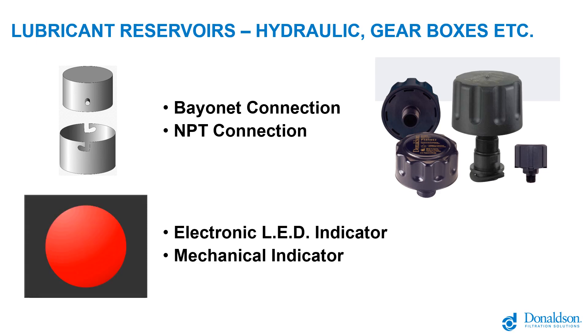There are also two indicator types: an electronic LED indicator and a mechanical indicator. The electronic LED indicator is activated by turning the TRAP upside down and pushing on the inside — the LED light will blink three times confirming activation and will not blink again until it's ready to be serviced. The mechanical indicator has a highly visible bright red band that shows when restriction reaches the point that it needs to be replaced.